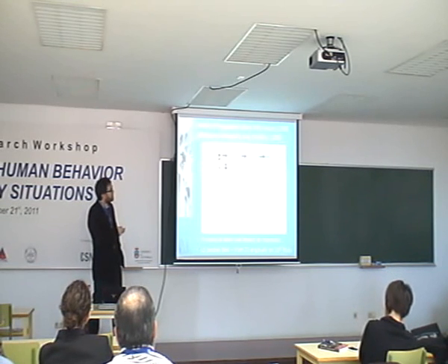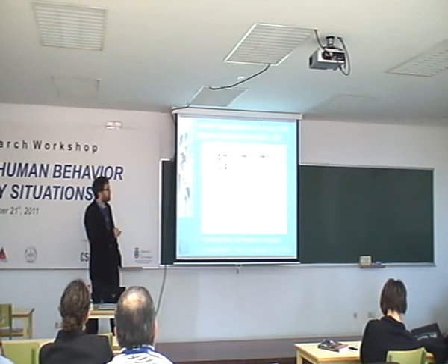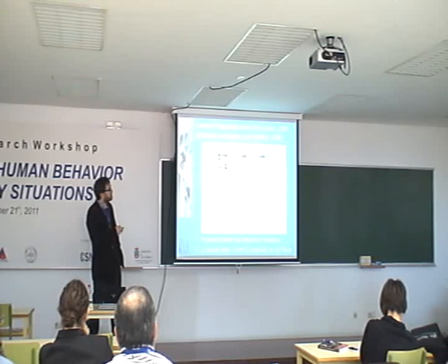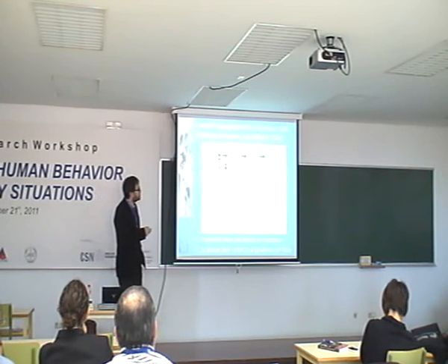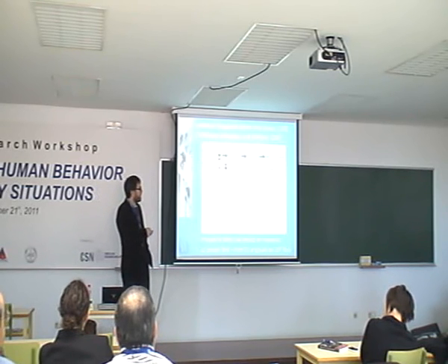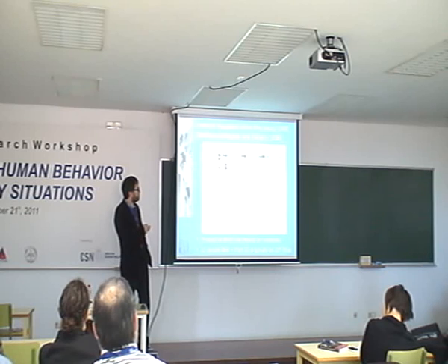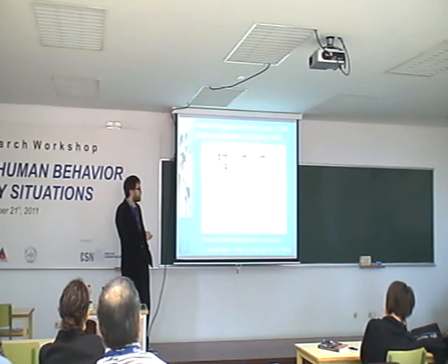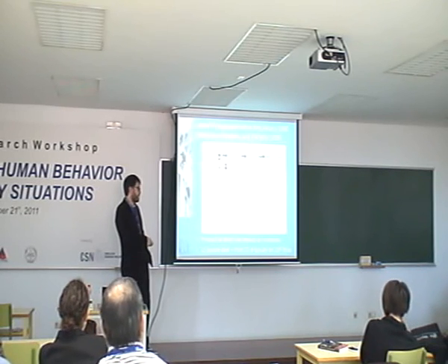Nothing happened up until 12:35. So we're talking about a relatively short period of time, 3 minutes. By this time, thin smoke was then seen on the 5th floor. Another 3 minutes elapsed, and then at 12:38, a general evacuation announcement was made. However, evacuation of staff on floor 5 commenced but failed. And basically 75% of the people initially on that floor succumbed.